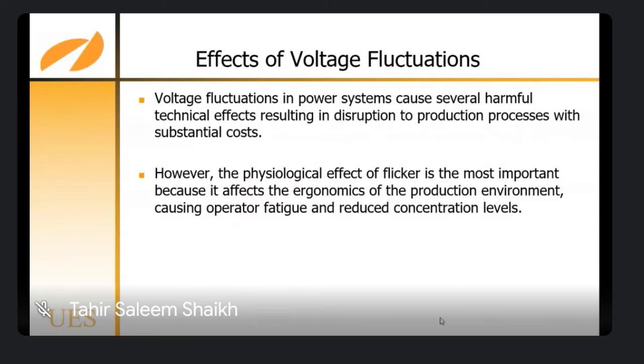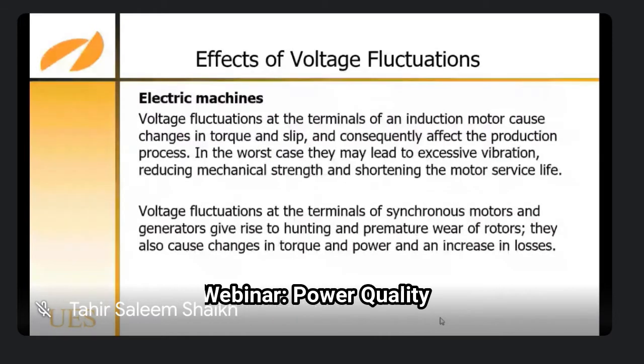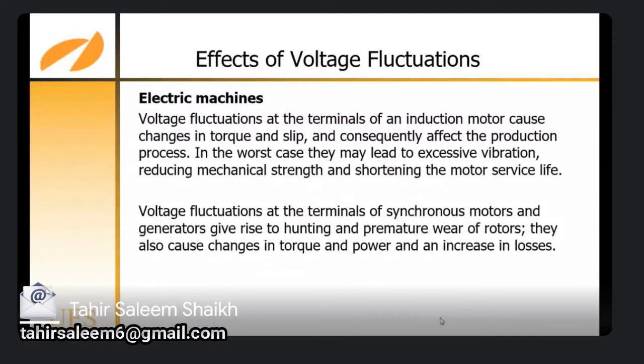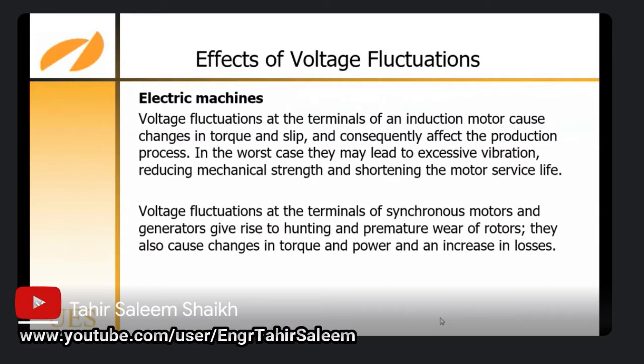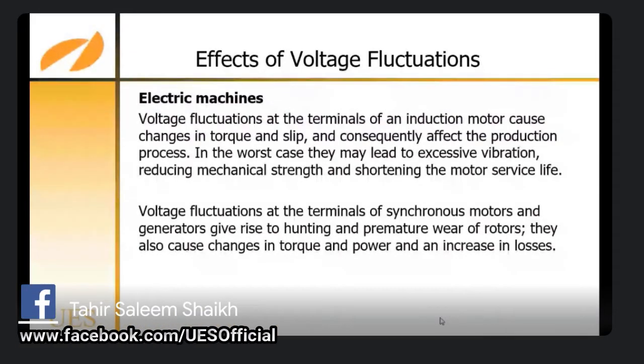Electric machines. Voltage fluctuation at the terminals of an induction motor causes changes in torque and slip because torque is proportional to the square of the voltage, and consequently affects the production process. In the worst cases, it may lead to excessive vibration, reducing mechanical strength and shortening the motor service life. Voltage fluctuation at the terminals of synchronous motors and generators gives rise to hunting and premature wear of rotors. It also causes changes in torque and power and an increase in losses. Even the efficiency reduces.